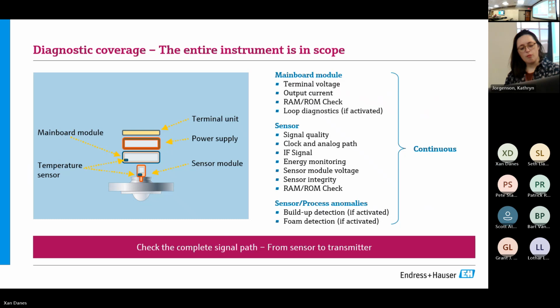Along with the simplification of the electronics, there's a very high drive to have much higher diagnostic coverage of those critical components. So we want to take this measurement and not just check the output of the device - we want to make sure every single piece of that hardware is operating exactly as it left the factory. This starts with everything from the loop itself, things like terminal voltage, current, loop diagnostics, but also signal quality, the analog path, the intermediate frequency signal - everything that really goes into the heart and soul of that measurement. We want to be able to trace that over time.